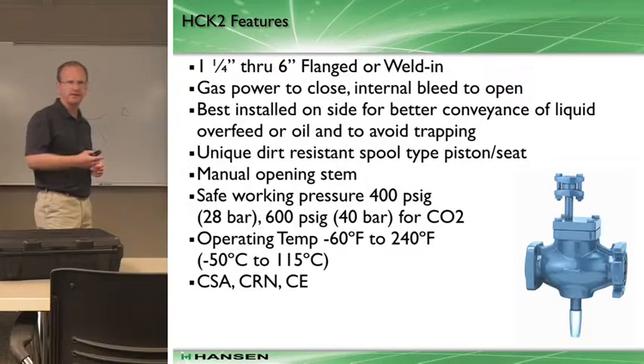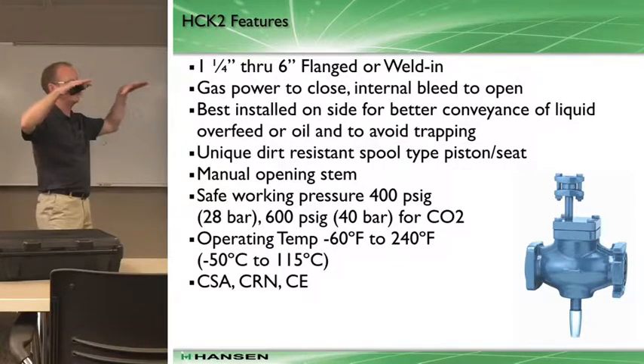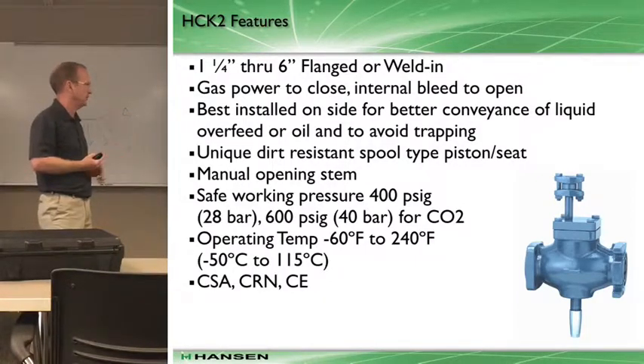Occasionally you'll see them on flooded evaporators - you'll see a gas-powered valve on both the liquid and the return. The liquid supply to a flooded evaporator back to the vessel. In order to defrost those vessels, you have to isolate both legs of the evaporator, so you'll see an HCK2-style valve there.